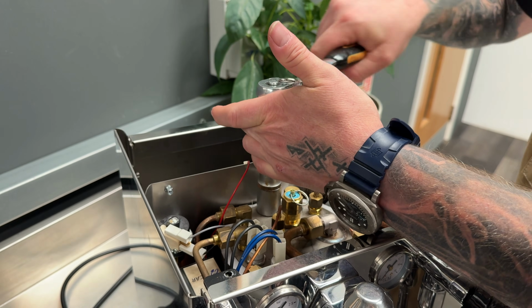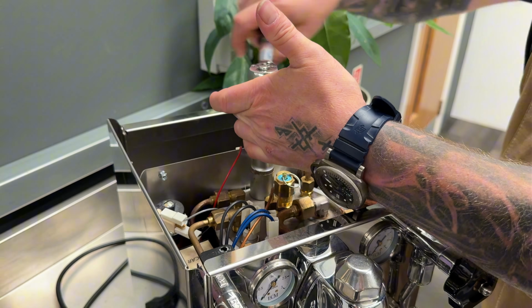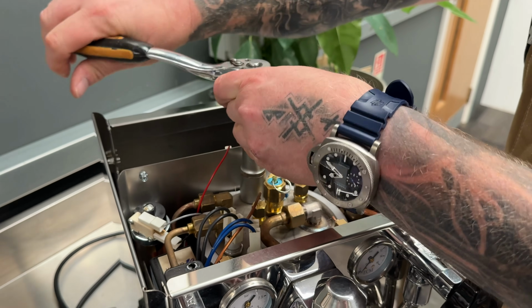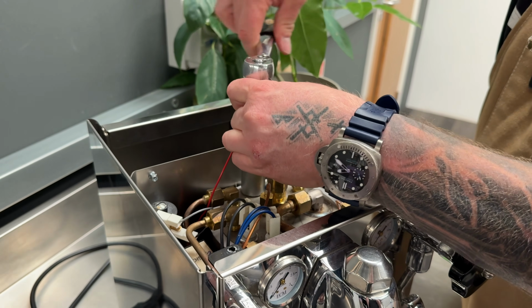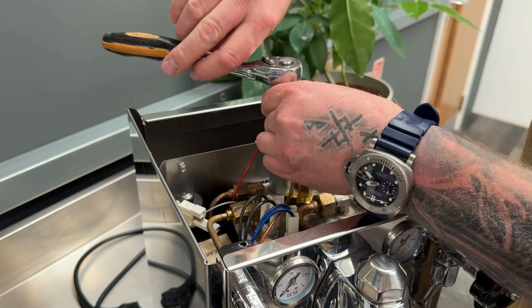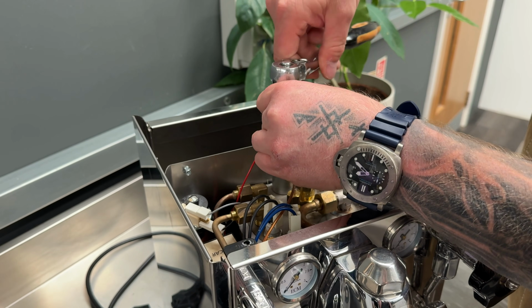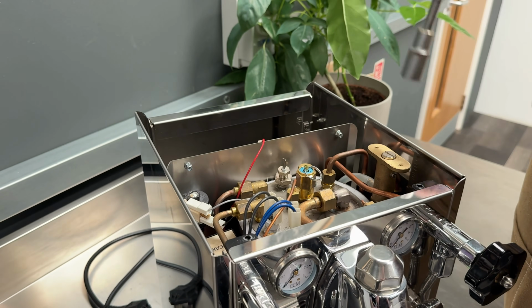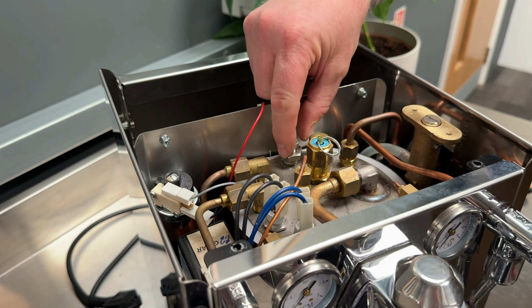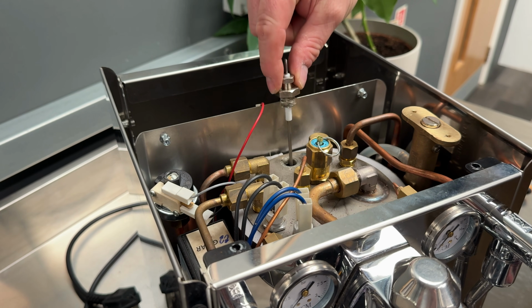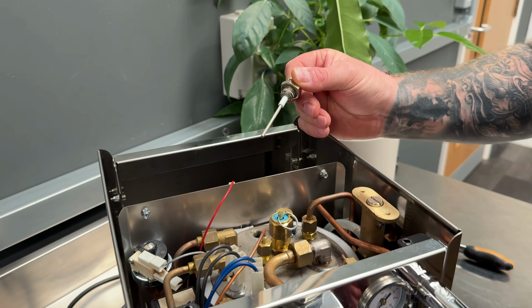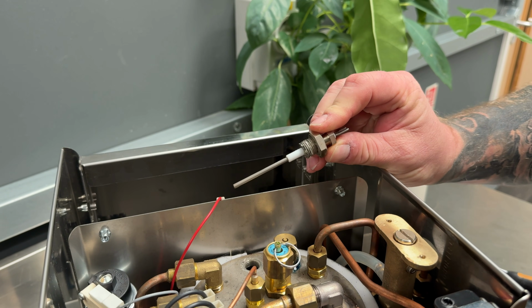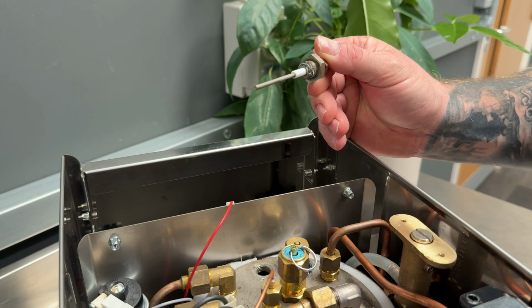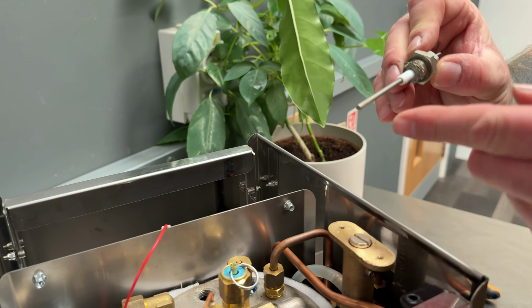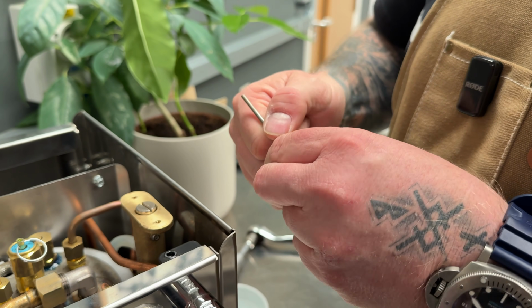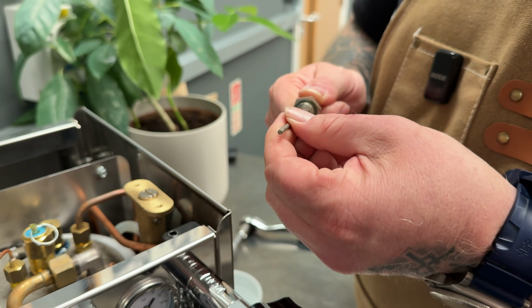You could also just pull the probe out without undoing the base nut, but that will actually knock any scale off of the probe and leave it in the boiler, which is not ideal. So we find it better to undo it from the bottom and then remove like so. And we can see that this probe is pretty clean, but if yours is covered in scale, then I would just clean it up using whatever method necessary.